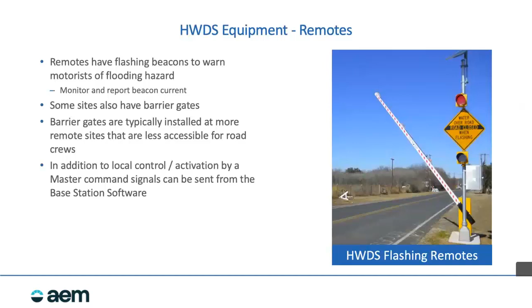Okay, I think we've pretty much addressed remotes. As far as communication, I mentioned we use VHF radio. We're using something called the Alert and Alert 2 protocol. Alert was originally developed by the National Weather Service for hydrologic data, and was originally intended as a one-way transmission. We developed the capability of using it in a two-way method for command and control, and have transferred that. There's now an updated Alert 2, which has much more robust forward error correction and a lot of enhancements to the protocol. VHF is far more robust than, say, spread spectrum or other technologies out there.